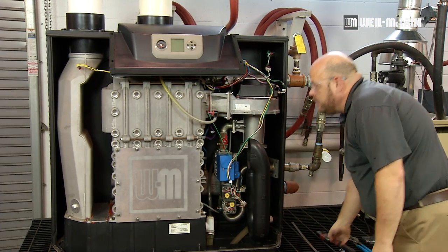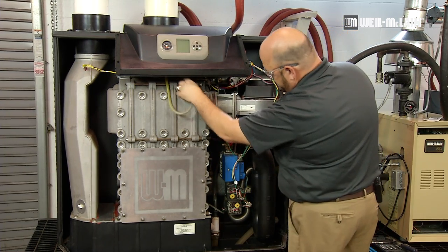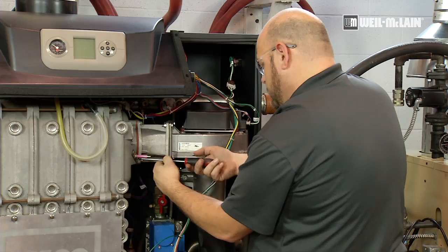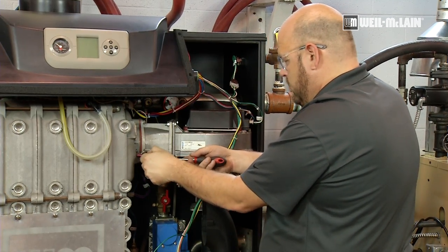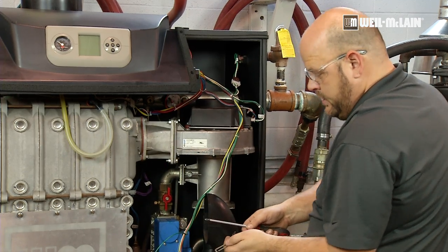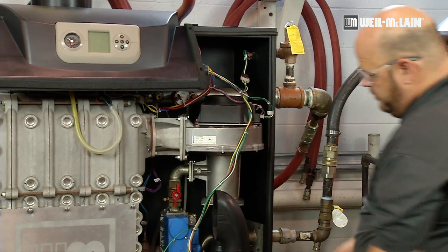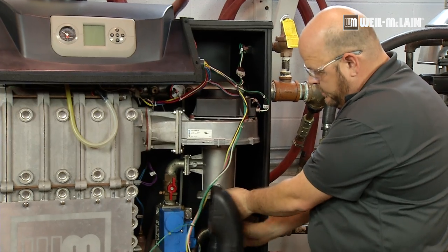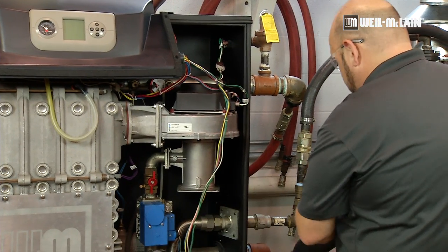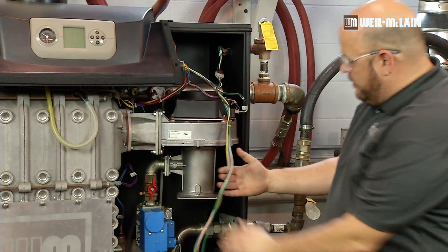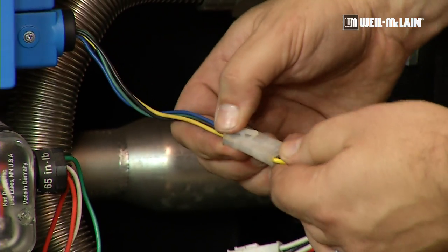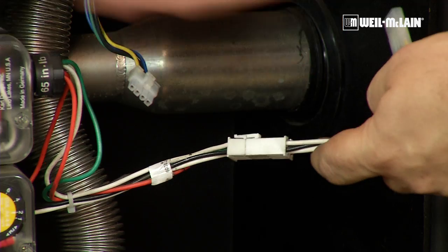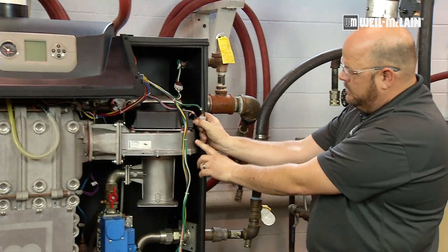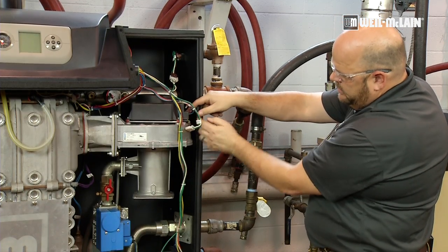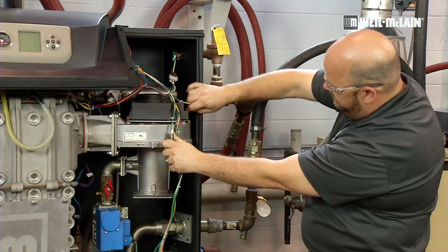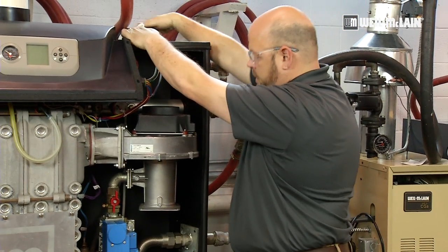We will start off by removing the ignition cable and the igniter, just to get it out of our way. And now we've got the igniter, and we'll set it to the side. Then we will remove the air inlet silencer from the unit, set it to the side, and finish taking our wiring off of our gas valve, the high and low gas pressure switch, the high voltage from our blower assembly, followed by the low voltage from our blower assembly. You can simply flip these up over the boiler.